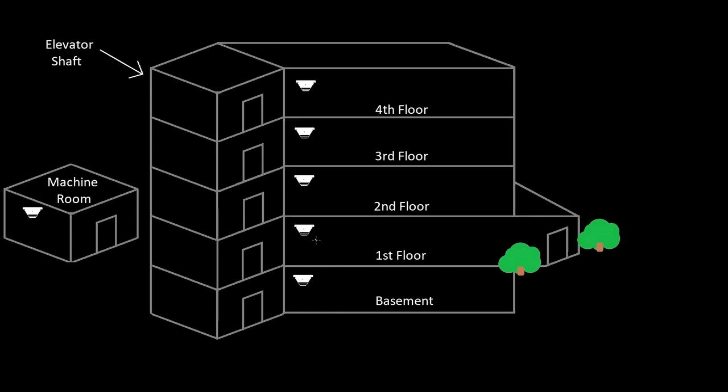The first floor is going to be in the second group that will send the car to the alternate floor. Which floor is the alternate floor is not going to be for you to decide. It's most likely either going to be the second floor or the basement - that's going to be building dependent. If the basement had, let's say it was actually ground level on the back side of the building or something and had an exit, then that would be the better choice. Otherwise it's typically the second floor.